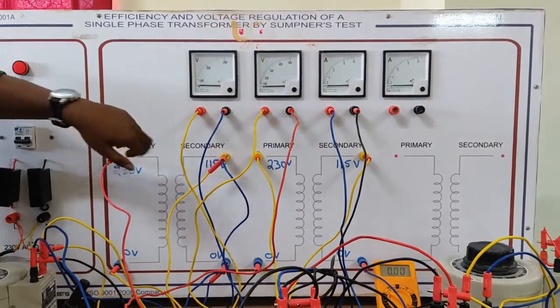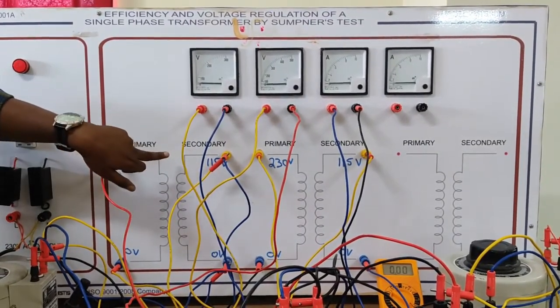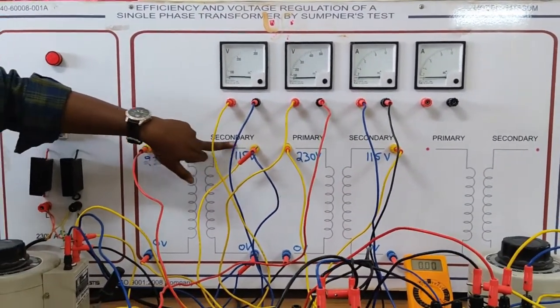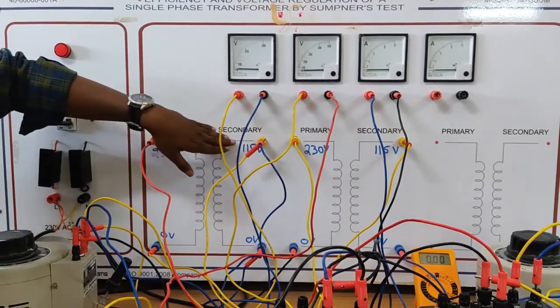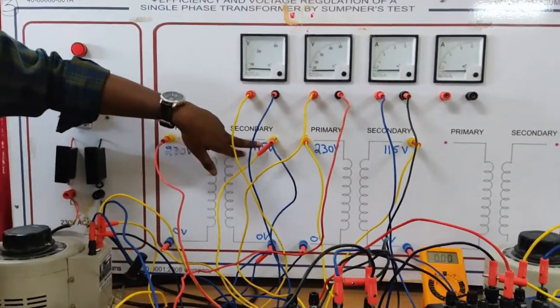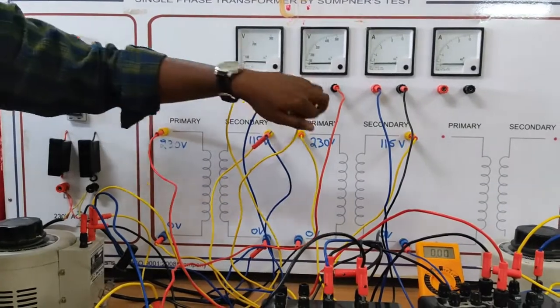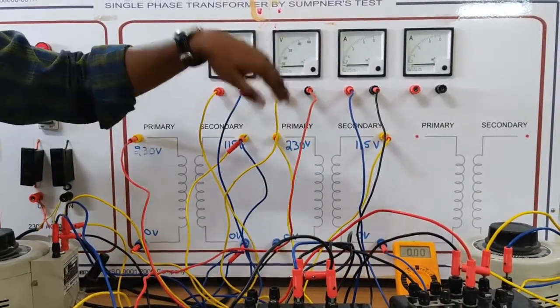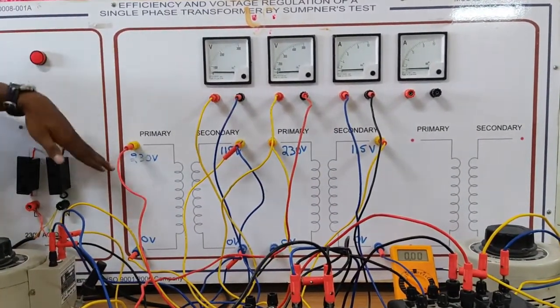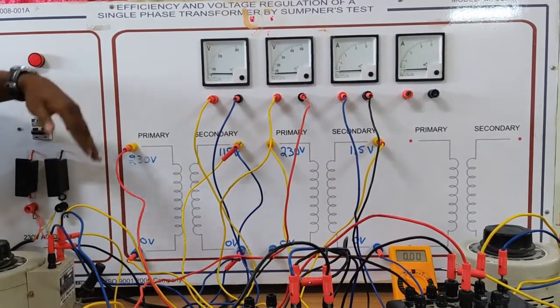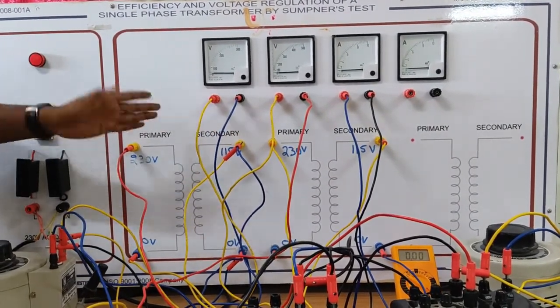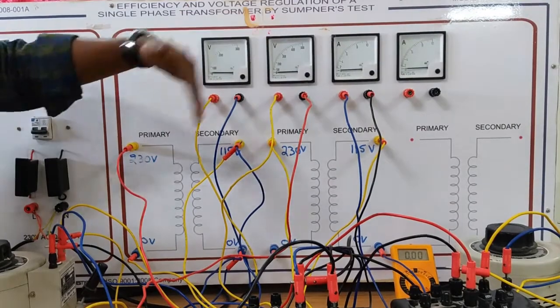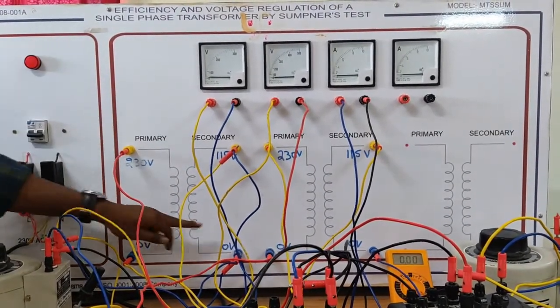I am assuming that these 115 as a primary. Actually, if you observe on the panel board it is mentioned as secondary, right? But I am taking this as a primary, meaning I am connecting the 115 of the first transformer and the 115 of the second transformer in parallel, and the remaining 230 volts terminals of both the transformers should be connected in series opposition.